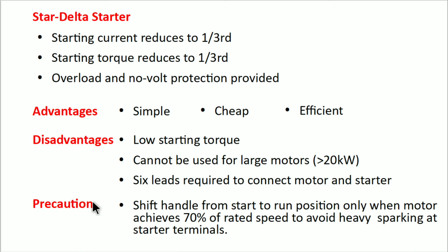The advantages of this starter are that it is very simple, it has low cost and is efficient also. The disadvantages of this starter are that the starting torque, as we have seen here, reduces to 1/3, which is already low, and further decreases.